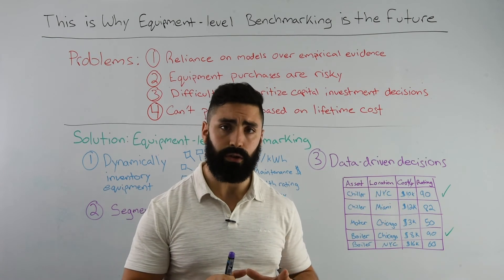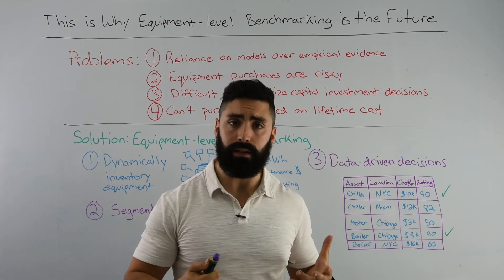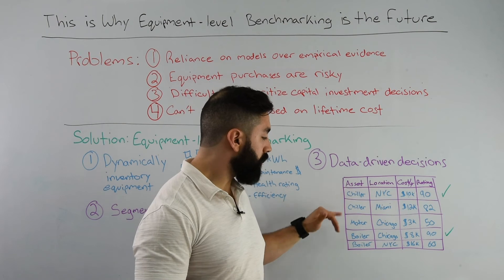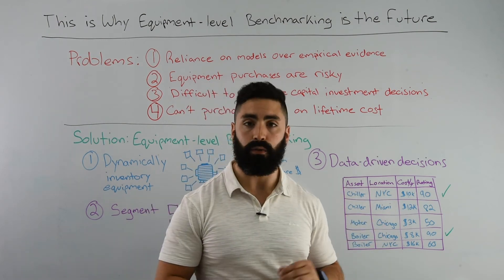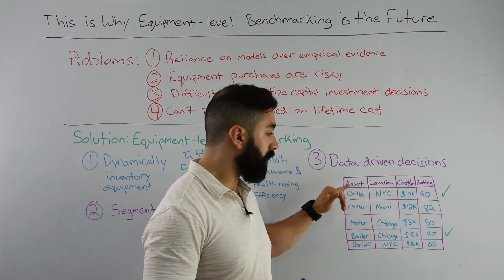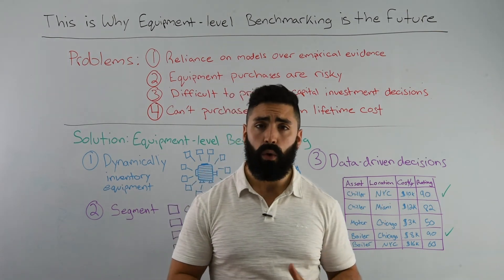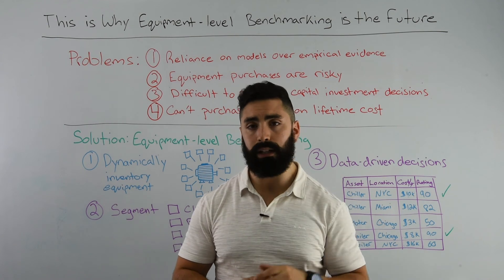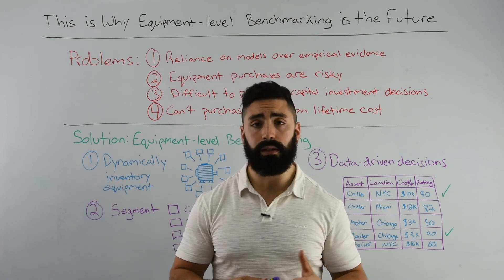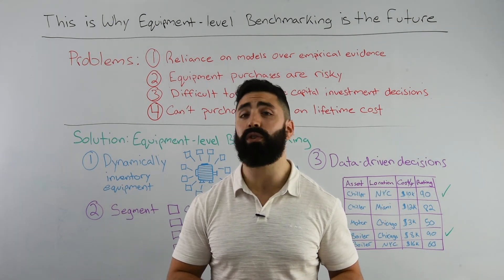Getting this granular data stream — which for us is done via circuit level power monitoring of all the house loads across the portfolio to create this inventory of systems — you can then get a data-driven ranking system to decide which piece of equipment may be most in need of a retrofit. Just because a system might be older or based in Miami where there's more salt in the atmosphere doesn't necessarily mean you'll need a replacement every five years. This ranking system tells you, based on various metrics, which pieces of equipment to pay attention to, therefore relying less on intuition and annual audits to know exactly what investment to make, when to make it, and what to expect from it.